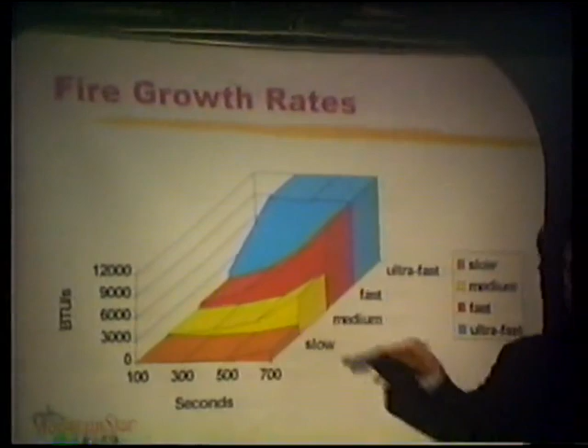NFPA 92B and NFPA 72 in the appendix put together a series of curves known as T-squared fires for slow, medium, fast, and ultra fast. Those are prescriptive rates of heat release that have been defined. And it's basically taking you to a point of when a fire will reach a given rate of heat release.